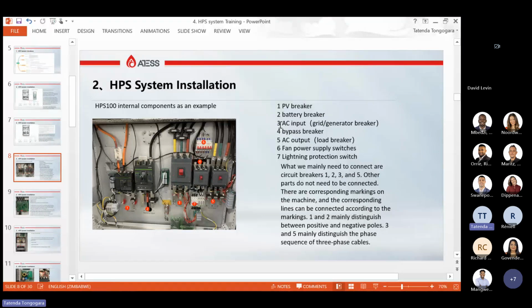And then there's something that I skipped here. We have our bypass breaker, that is number 4. So in the event that you want to bypass your system, you can bypass it here with number 4. You switch off everything and then you switch on MCB number 4 to bypass. If you're doing any maintenance work, you can bypass with bypass number 4. But for you to bypass, you need to make sure that everything else is off, and then you switch on your bypass. So your AC input will just go straight to the bypass and to your load.